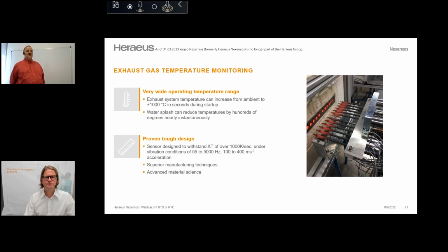And again, the sensor continues to perform. It'll basically model a long use cycle. And again, our sensors pass this test. We have a sensor that can be used to 1,000 degrees C under these conditions, and works with very high stability and high accuracy.